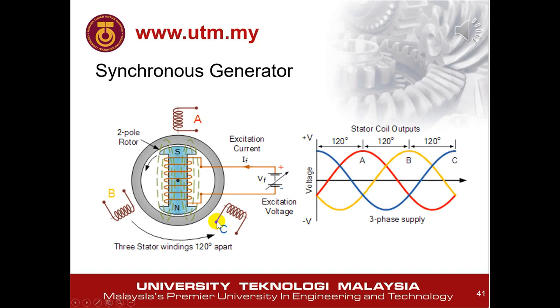Here is another figure showing how the exciter supplies current to the rotor. When the exciter current passes through the rotor winding, the rotor becomes like a magnet, and as it spins, it induces voltage at phases A, B, and C, which are placed 120 degrees apart. As a result, the induced voltages have different phases because the stator windings are 120 degrees apart, so the phases are also 120 degrees apart.